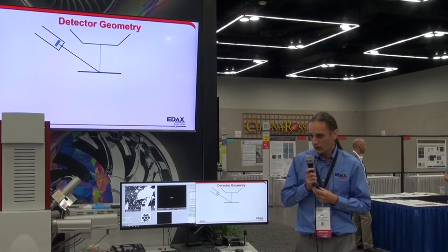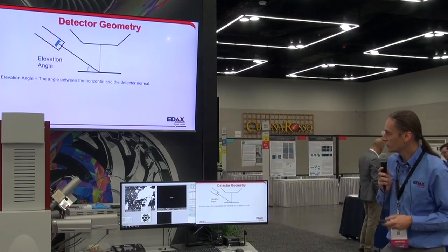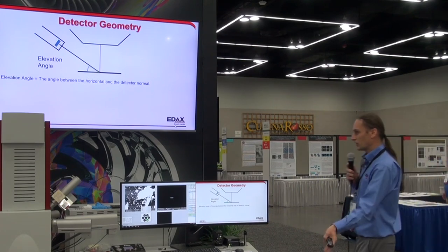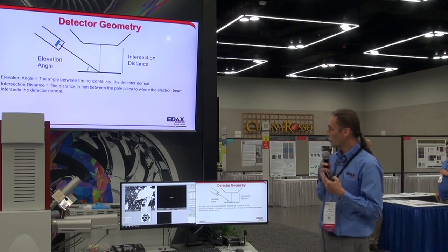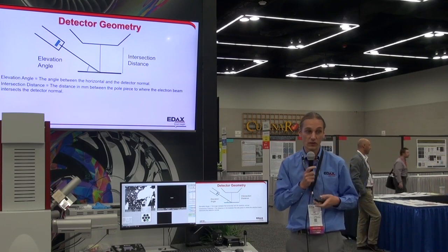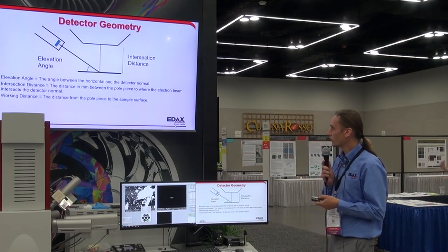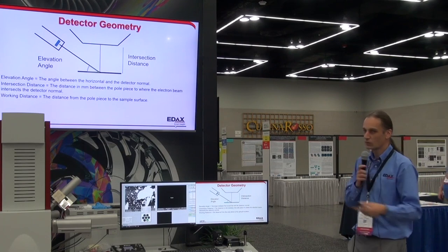The geometry of the system also has an effect on the background. We have what we call the elevation angle — the detector typically comes in at an angle of 35 degrees into the chamber, and the elevation angle is the angle between horizontal and the detector normal. We have the intersection distance, which is where the normal to the detector coincides with the electron beam — basically the sweet spot of the microscope for the most efficient x-ray collection. The working distance is the distance from pole piece to sample surface. At ideal conditions, the intersection distance and the working distance are the same.